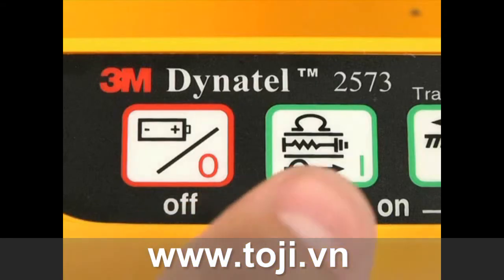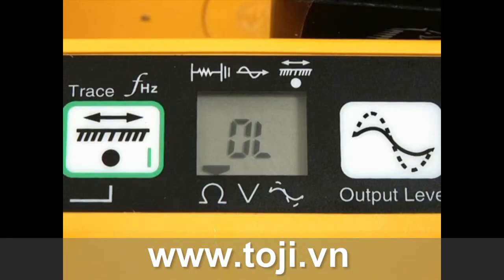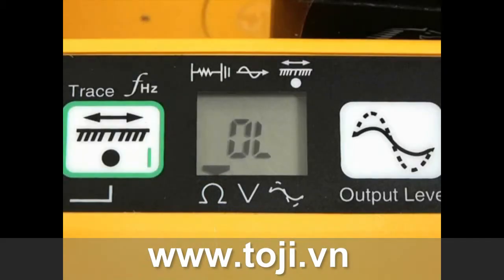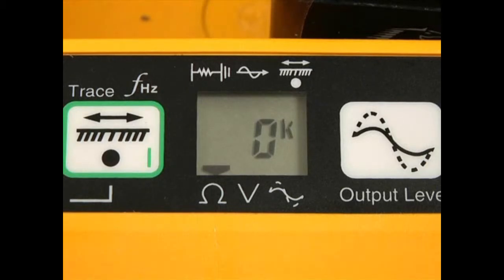Press the second key on the transmitter, which is the ohms key. A flag will light in the display above the ohm icon, indicating that the transmitter is in ohms mode. A resistance measurement will appear on the display. The lower the resistance of the fault locating circuit, the more severe the damage is to the insulation of the conductor. If OL appears on the display, this is an indication of an open line. This indicates that there is not an earth return fault on this conductor.